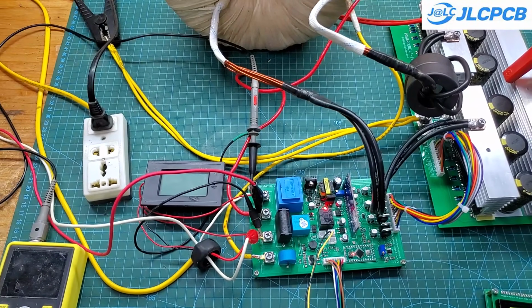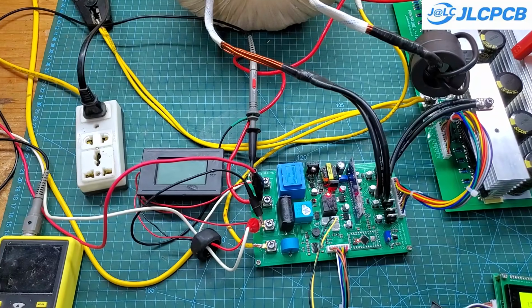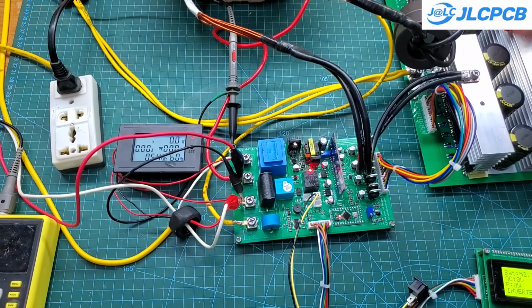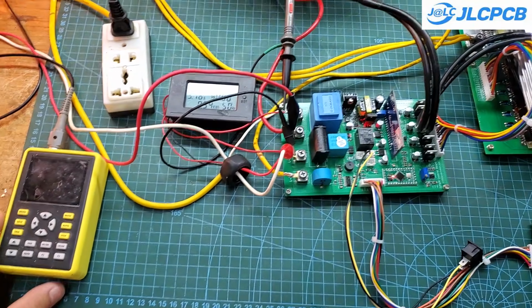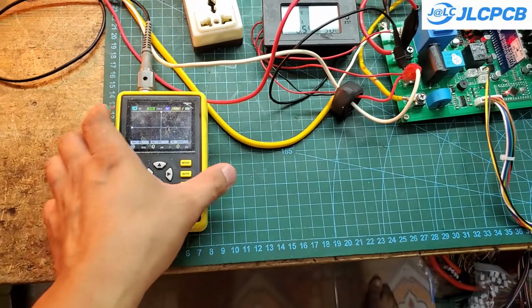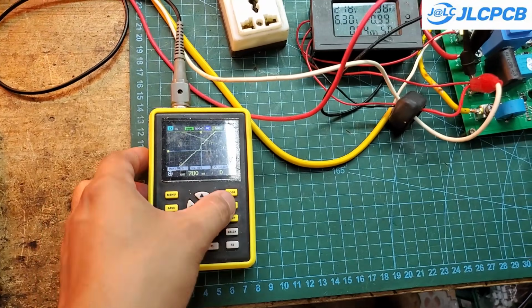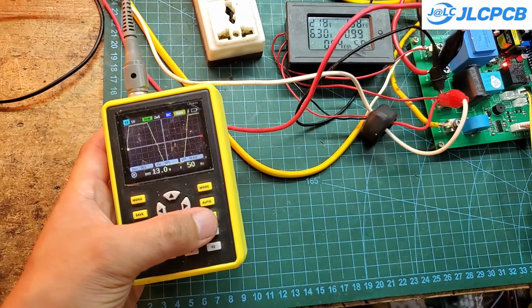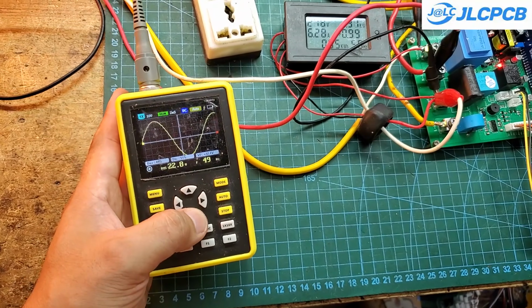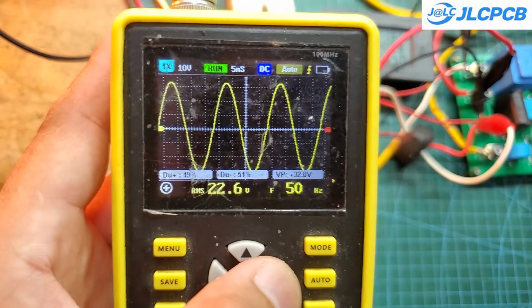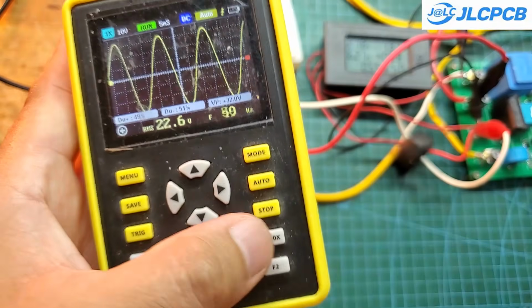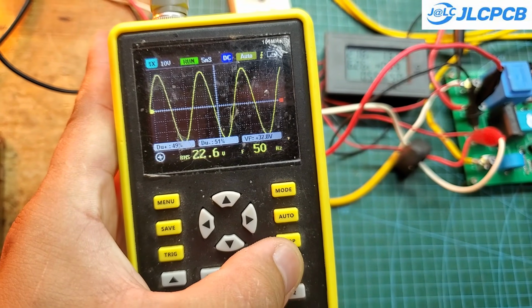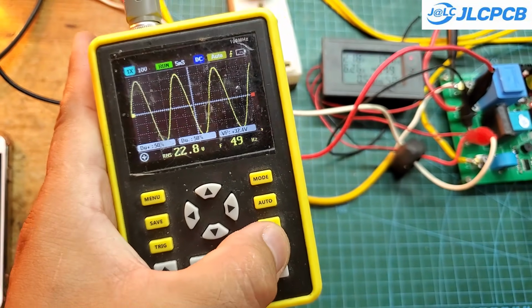Finally, by simply connecting the transformer to the control board and power board, we have a completed 48-volt inverter with a 7.5 kVA output. Here I'm testing it with 2 light bulbs with a total load of about 1,300 watts. The peak efficiency reaches up to 97%, and the full range efficiency is 94%, which is very high compared to other low-frequency inverters on the market.